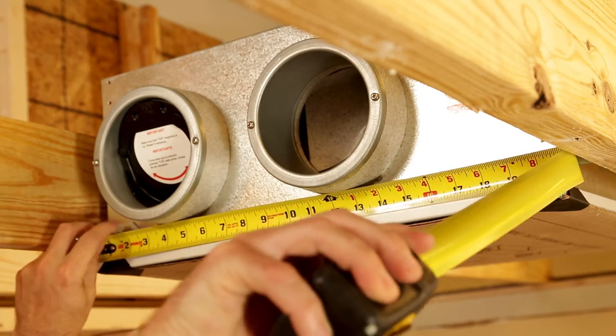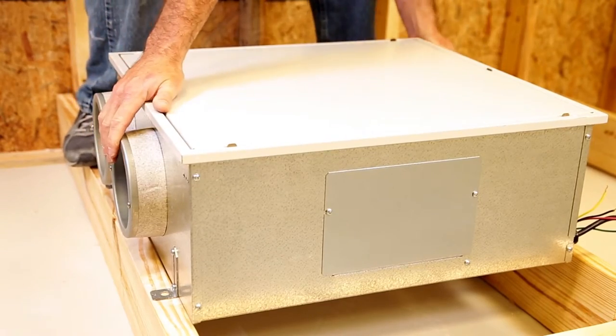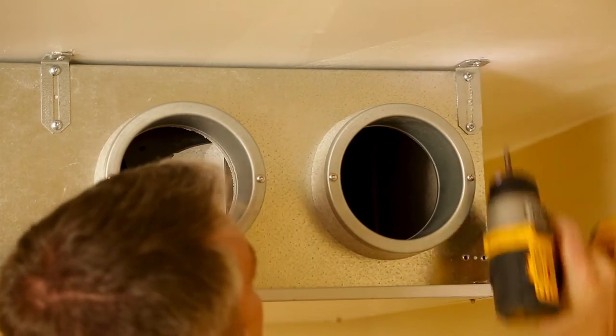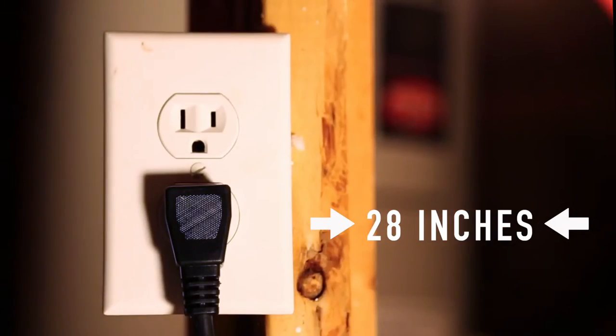The ERVS-100 can be mounted in the ceiling, in an attic, or in a small closet or mechanical room. Regardless of where the ERVS-100 is installed, there must be a standard three-prong electrical outlet within 28 inches of the unit that must be connected to its own dedicated circuit.